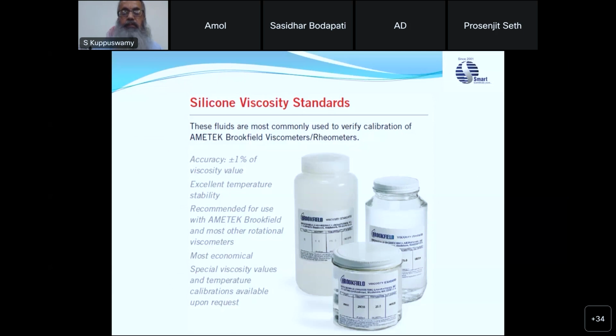And these are some silicone viscosity standards used for calibrating the viscometers. Not only silicone viscosity standards; depending on the application or type of viscometer, different standards are there. Mineral oil standards are also available. Next.